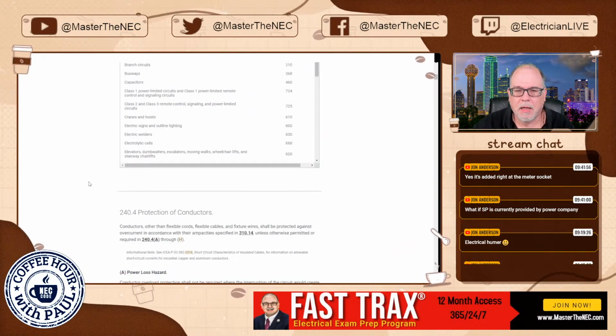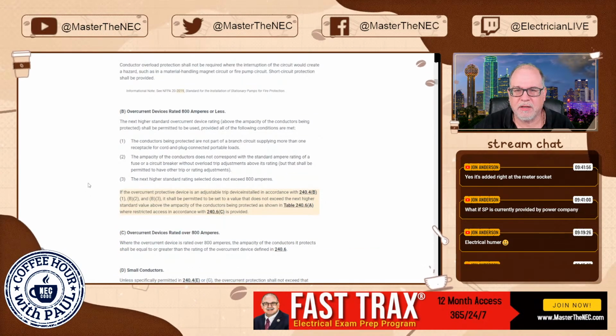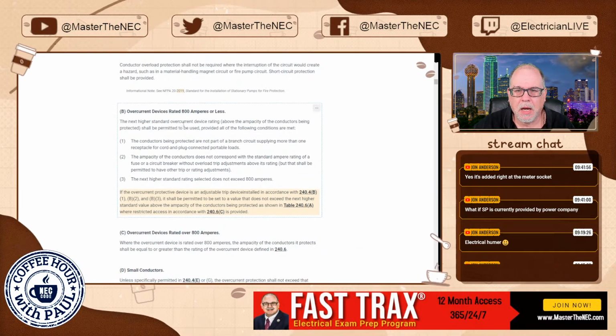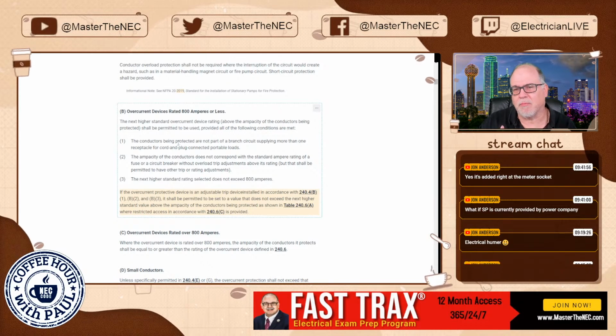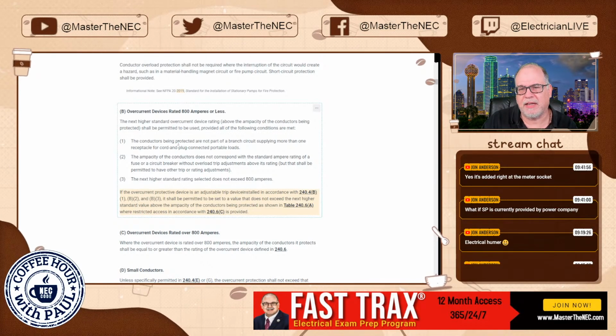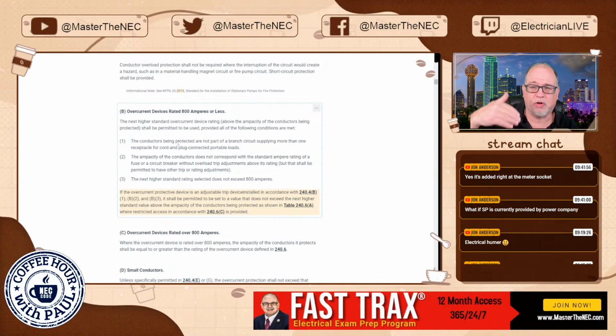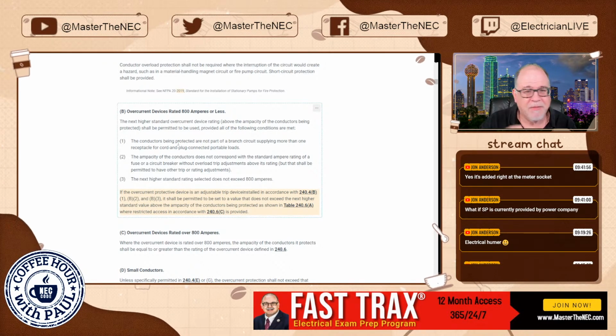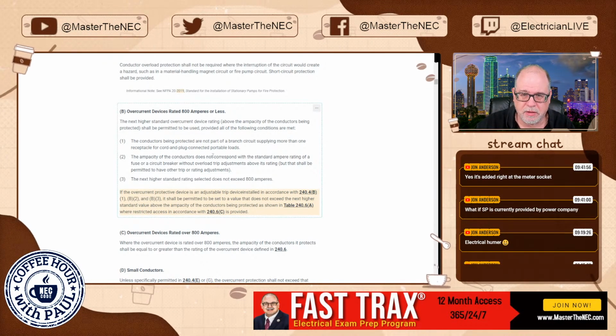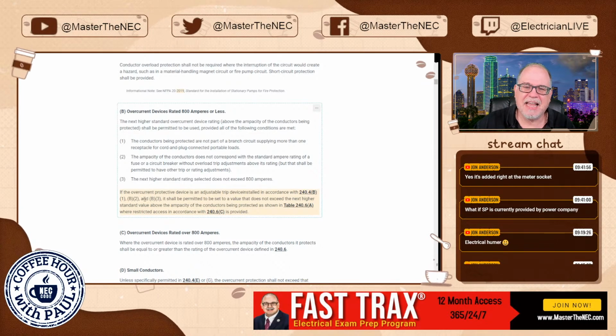Okay. Let's see here. Getting into significance here. Y'all remember the next size up rule when it's rated 800 amps or less? The next standard size overcurrent device can go, okay? That didn't change. Still the same rule here. But they did add this information down here.